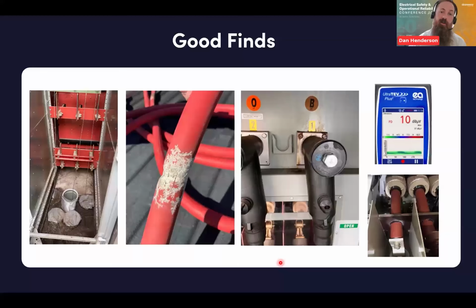I'm just going to quickly cover some good finds. These are from experience, finds that we've captured. This one is an external HV switch, which was fairly new, so it was given a 5-year category 1 process, and then some levels of PD were being indicated within 3 years. On removal of the cover, it turned out that the duct integrity had something go wrong there, whether it's rodent ingress or something. The vents as well had started to deteriorate, so they started letting dust and debris in. On those bushings inside, you were getting a level of dust and debris, and there were fine levels of tracking. So you're getting PD and tracking on those bushings, and that was picked up before it failed, which is ideal.